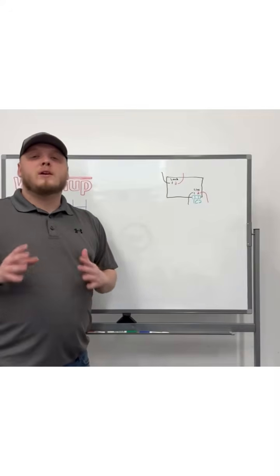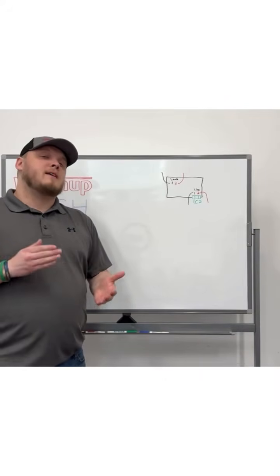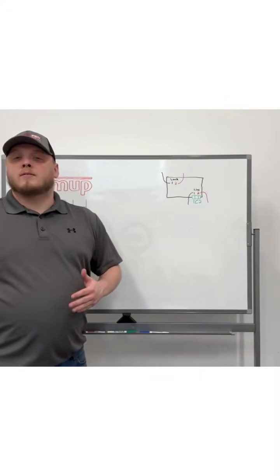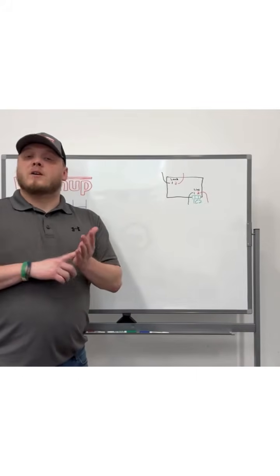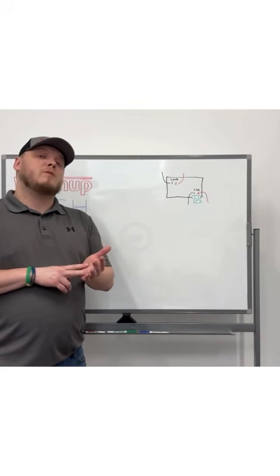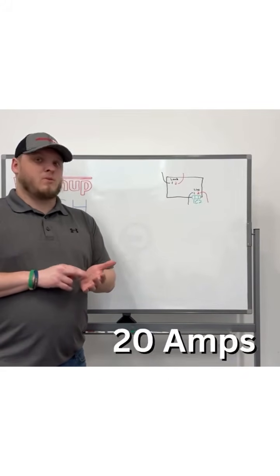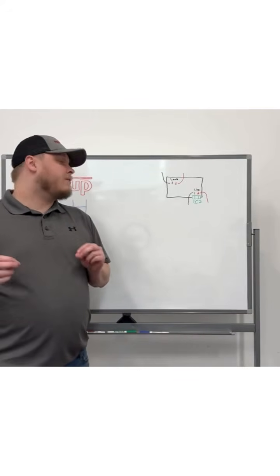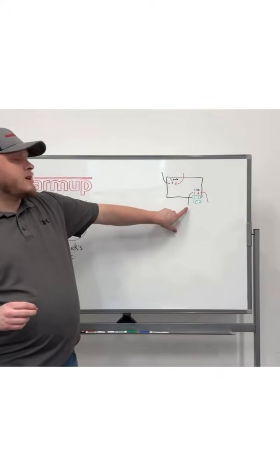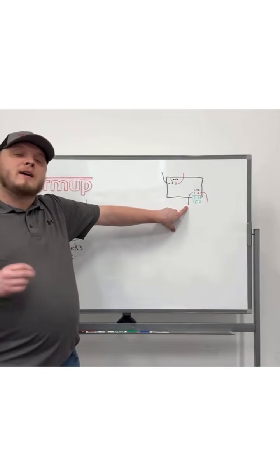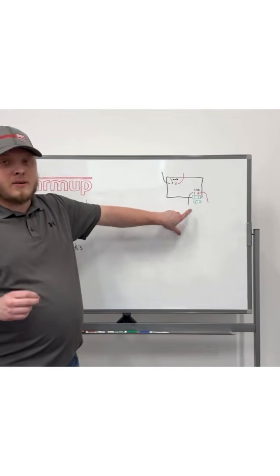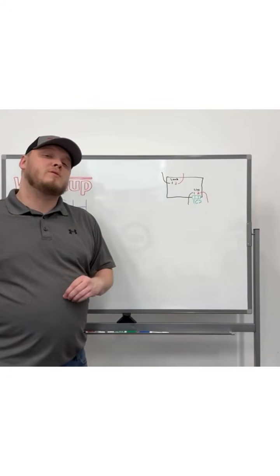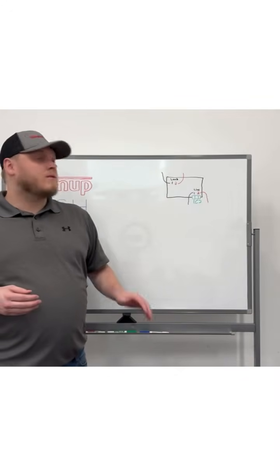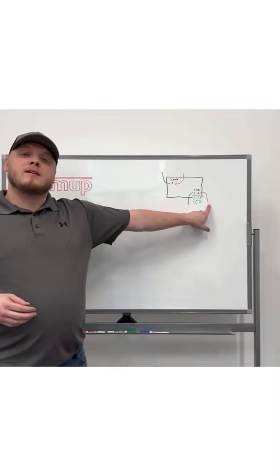Every floor heating thermostat has a dedicated circuit to your breaker panel. That breaker, whether it be 120 volts or 240 volts, we always recommend to be 20 amps. The hot from your breaker will go down to the line side of the thermostat, and that will connect to the black. Your second hot for 240 volts or neutral for 120 volts will go to the red.